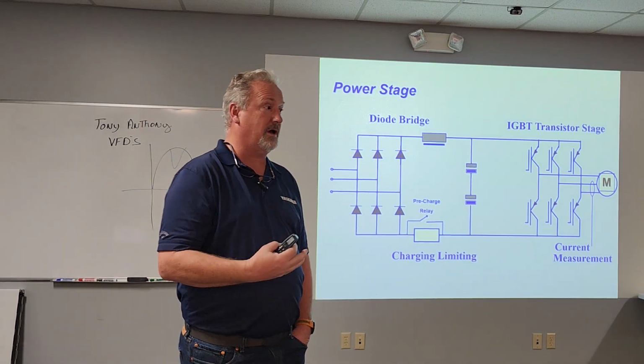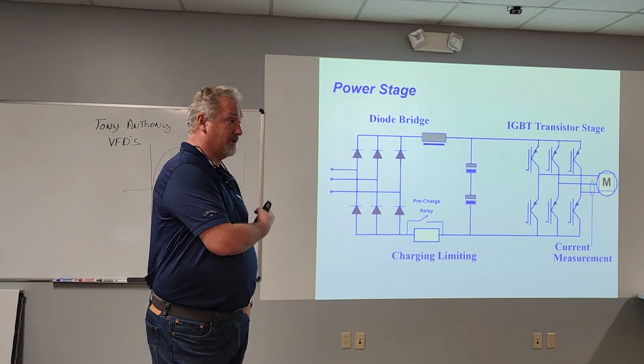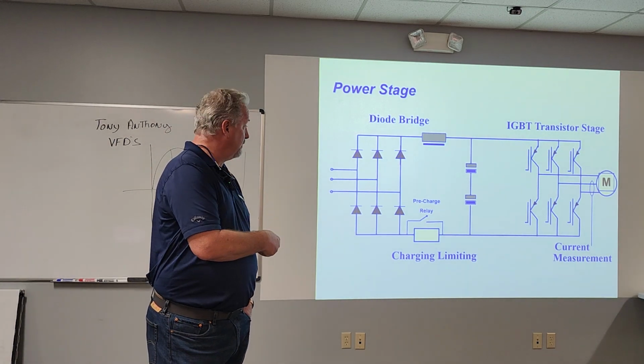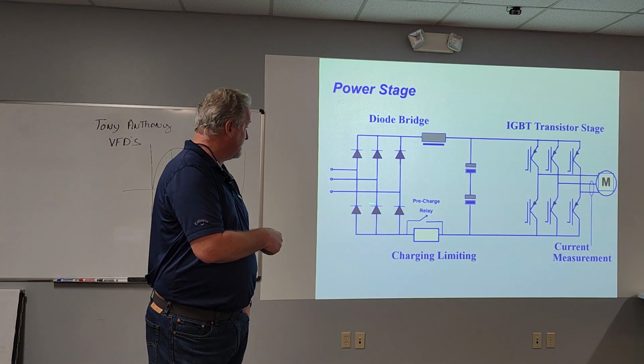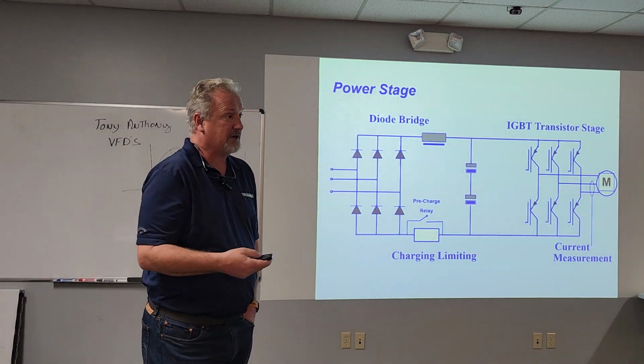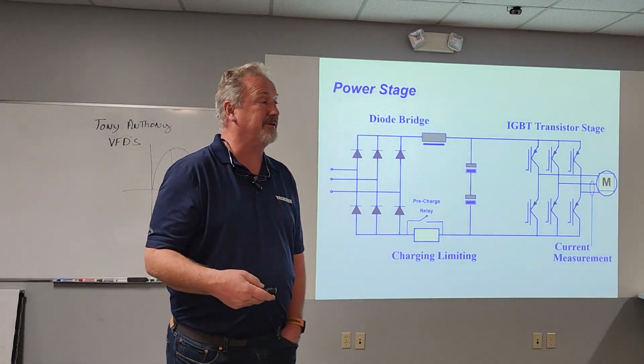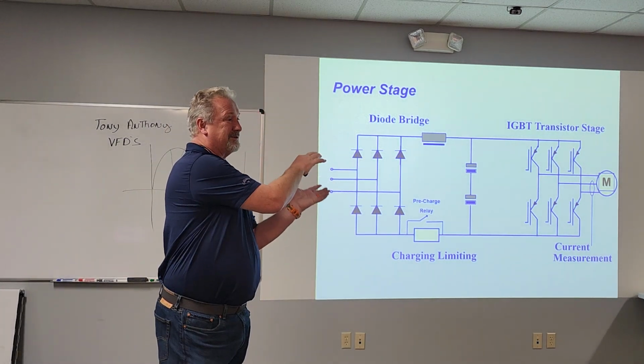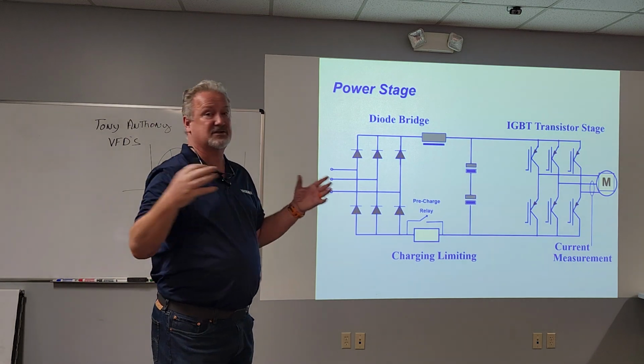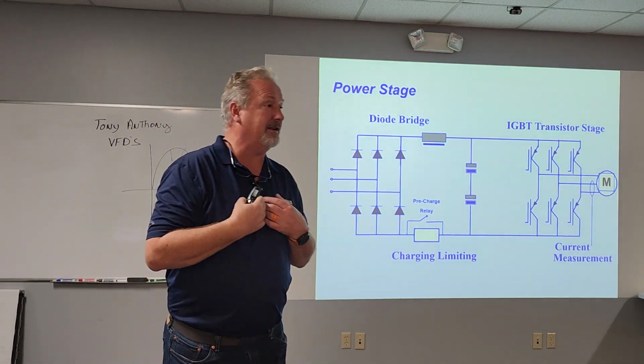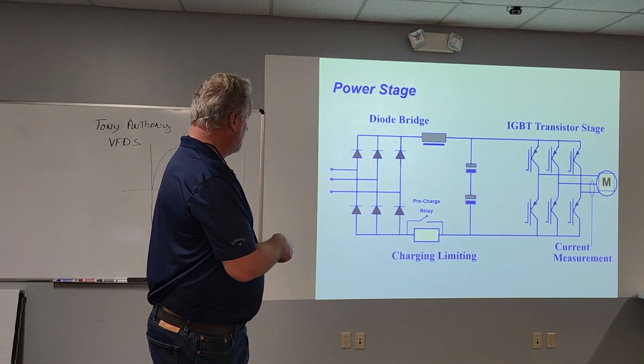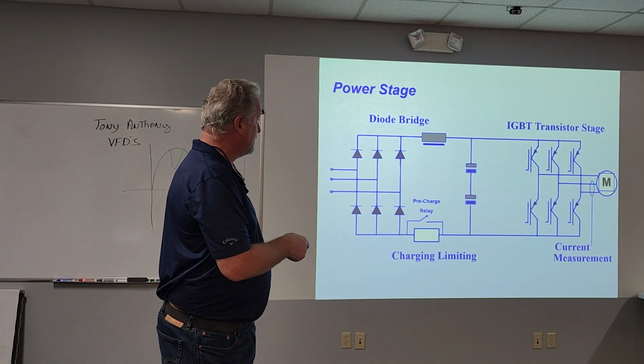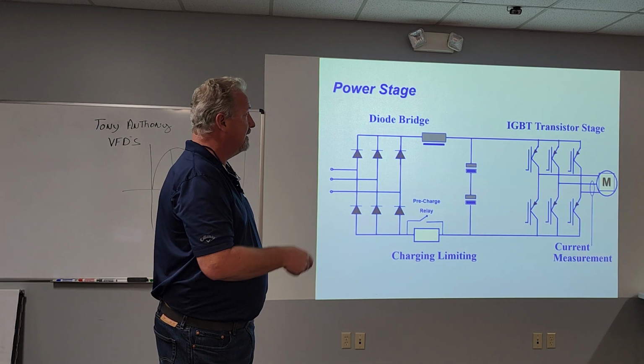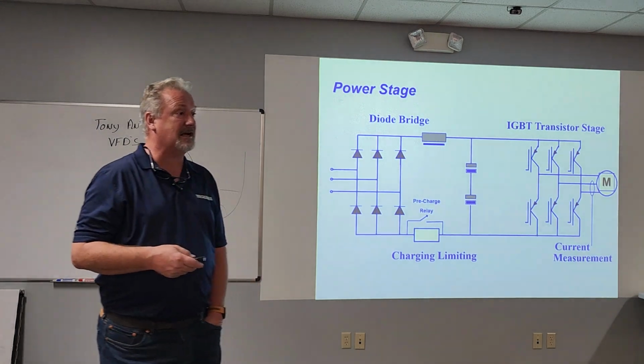So you can run drives off single phase. You'll bring power, you bring your 2 legs into L1 and L2 usually is the most common. The thing you got to remember though is now you've got all that current coming in 2 legs instead of 3. We have to oversize the drive. Whether you got 3 legs or 2 legs of power doing it, we're still going to create that DC bus. These are still going to fire and create the 3-phase output.